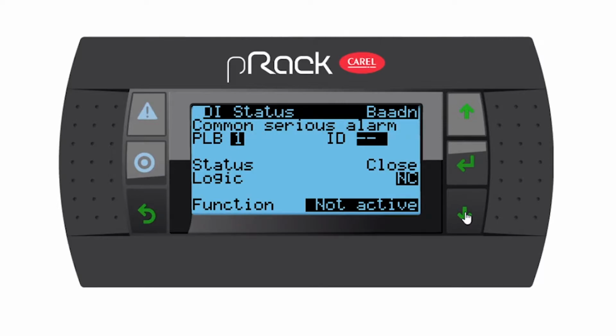Common serious alarm. Yes, remember as per my notes I said we have a common serious alarm. So I'm going to assign it, not to the U's, that's universal inputs. I'm going to assign it to ID 18. This is going to be my last relay on the pRack board, and this is a large pRack board. It's going to be normally closed, and as you can see the function is not active, which means this alarm is currently not active. If we do have an alarm currently on the serious alarm on the pRack, and you go to this page, you will see it will say active, and that relay will be either open or closed depending on your logic. So let's go down.